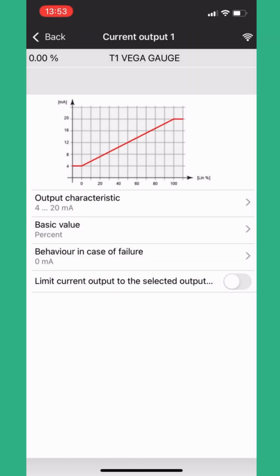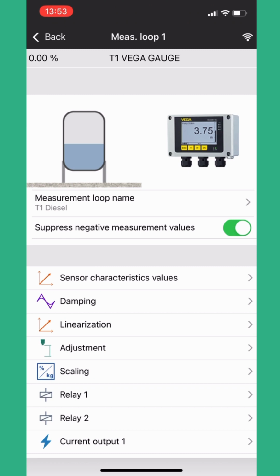We're also going to change the current output. So the VEGAMET has a 4 to 20 milliamp output to allow you to output percentage or linear percentage to a third-party device such as a BMS or an Internet of Things controller.